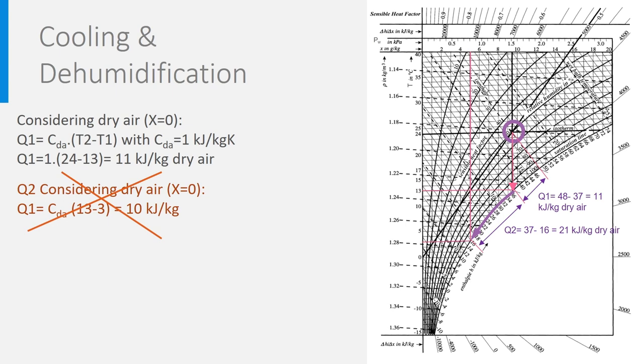Let's consider the full equation for the enthalpy. We can derive easily that H2 equals 37 kJ, while H1 is 15.5 kJ per kilogram. The needed heat is therefore the difference, which is a bit more than 21, very similar to what we found in the diagram.